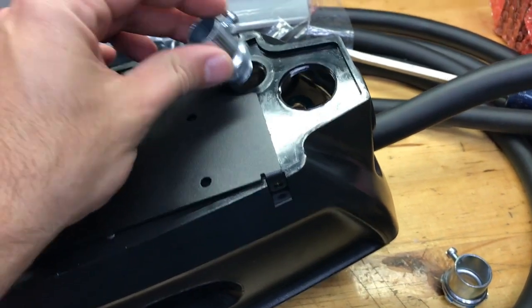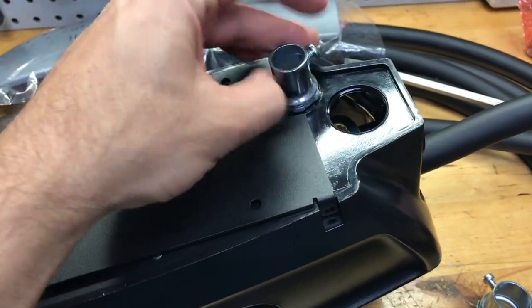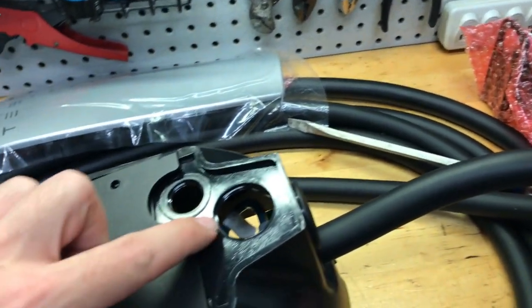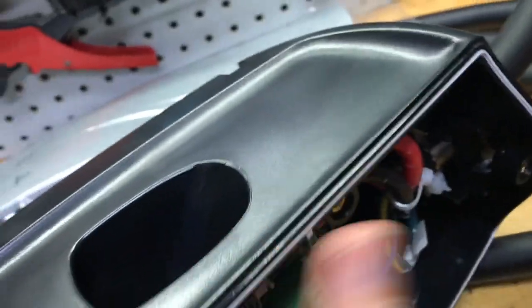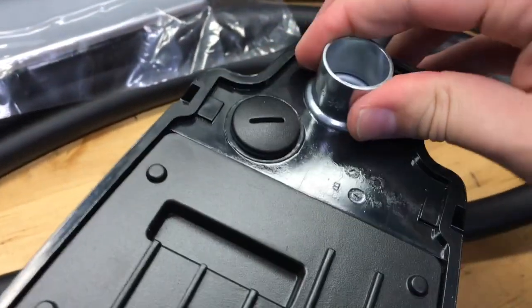The signal port is a half-inch conduit EMT that screws right in. Of course, we can't run our two 6-gauge cables through that, so they provide this one-inch conduit. A three-quarter-inch set screw adapter fits right in with the nut on the inside. It's a little bit loose — we're going to caulk this up to seal it from the elements, but that is a very nice fit when it's tight.